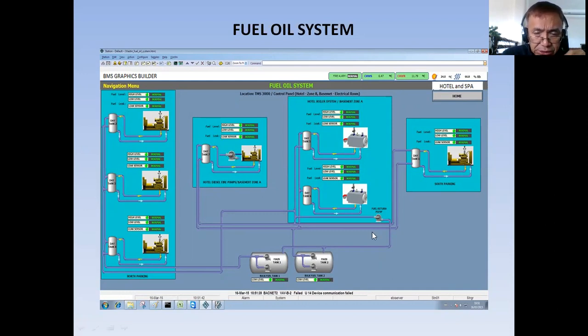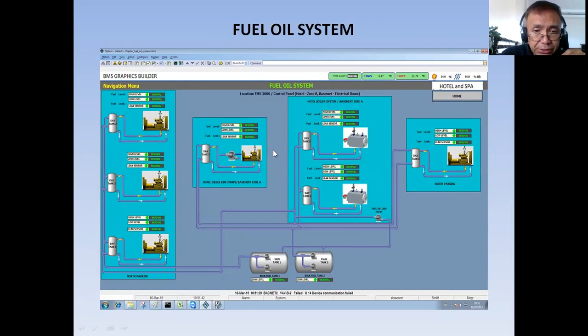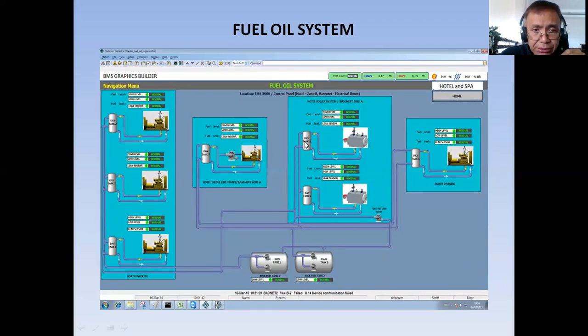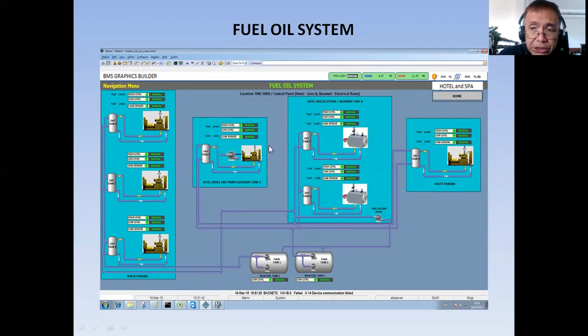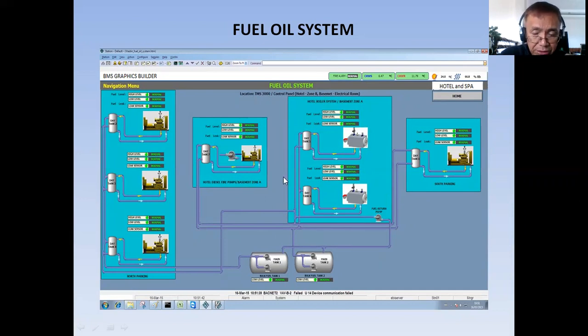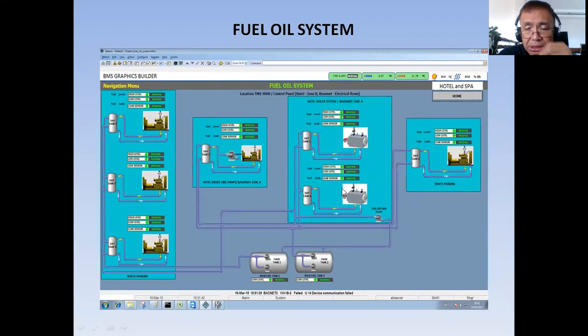This is basically how you are going to design your fuel oil system for the project. The panel that manages this fuel oil system is the TMS 3000. What I have done here is to get the points from software integration. The protocol that we use here is BACnet over IP. So typically, this is how you are going to prepare your fuel oil system BMS graphics.